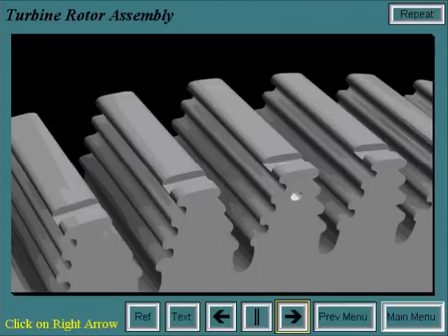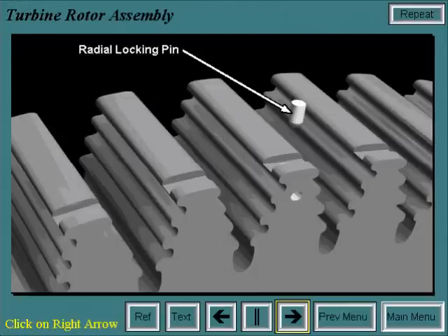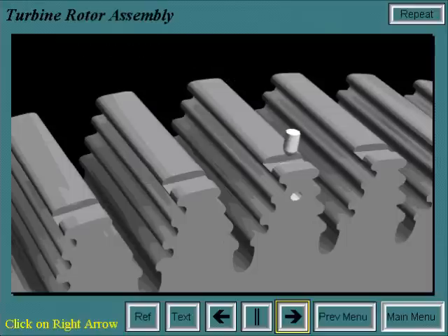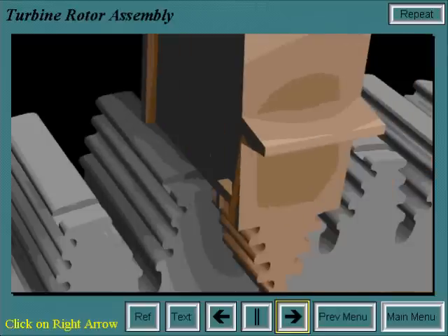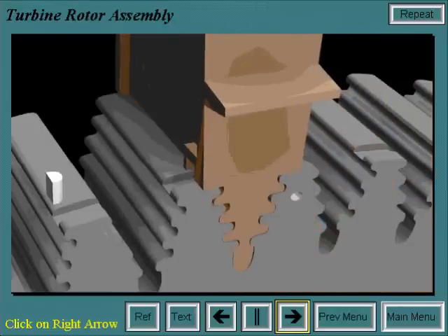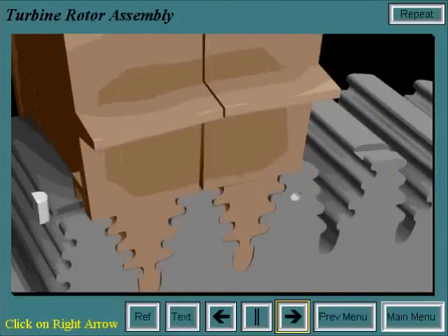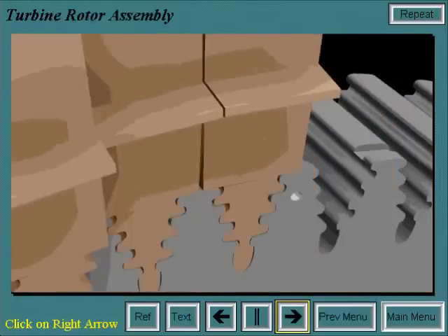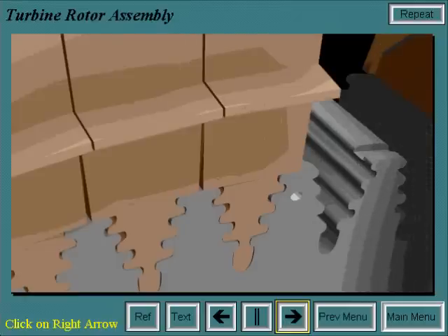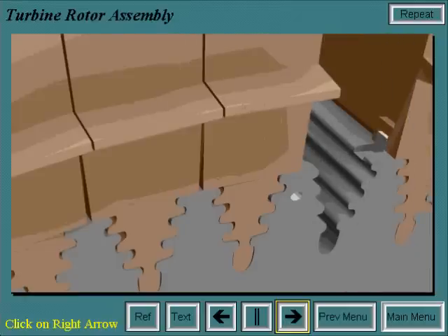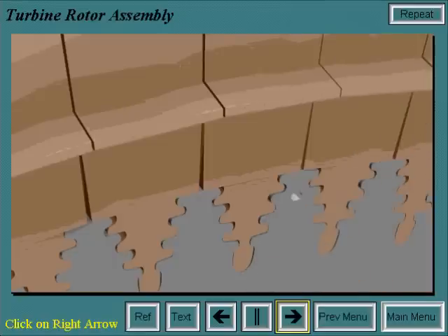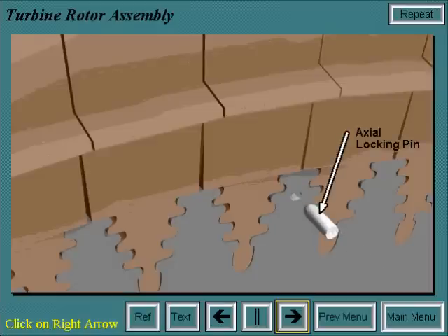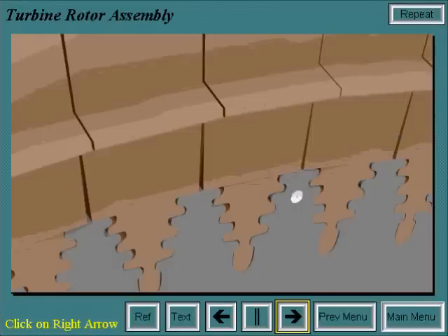The first step of assembling the first stage buckets to the turbine wheel is to insert the radial locking pin into the locking bucket dovetail. The first bucket is installed in the counterclockwise adjoining dovetail slot and is held in place with a D key. The remainder of the buckets are installed in this fashion, working around the wheel counterclockwise. The last bucket is installed into its dovetail and the axial locking pin is driven into the wheel, pushing the radial locking pin up to hold the last bucket in place. All the buckets are now locked onto the turbine wheel.